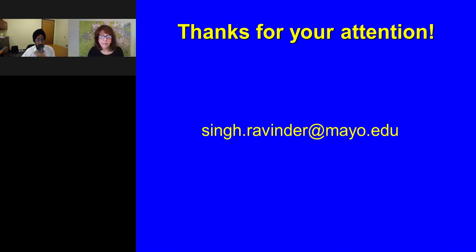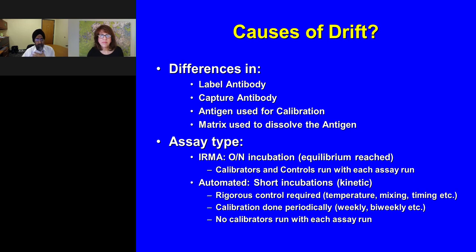Thanks, Judy — it's a very good question. Because of competition among manufacturers and commercial labs, everybody is using different recipes. There is no consistent supply of calibrators or reagents, and all of this adds up to different recipes for different assays. It will be hard to standardize assays until all stakeholders sit down, meet, and address this together.